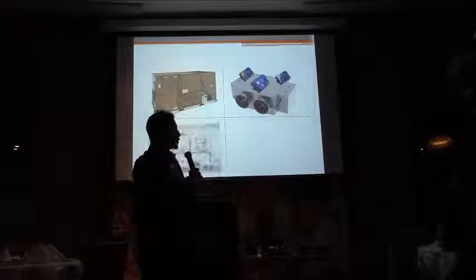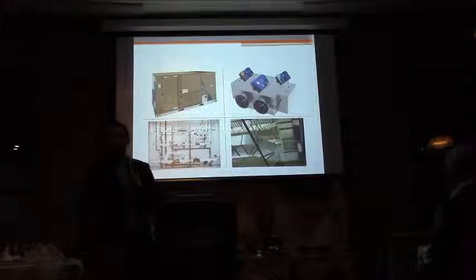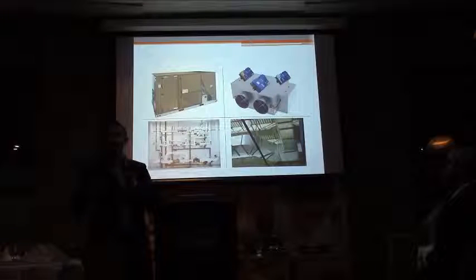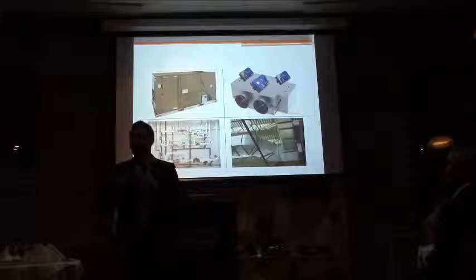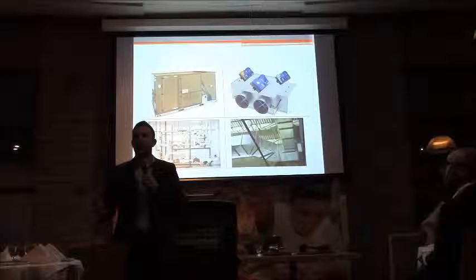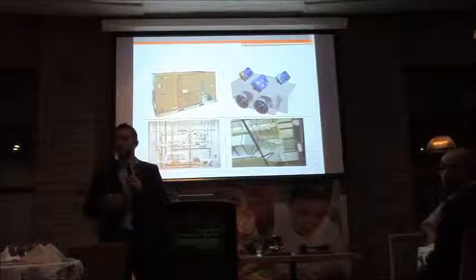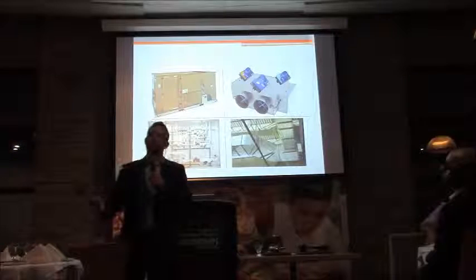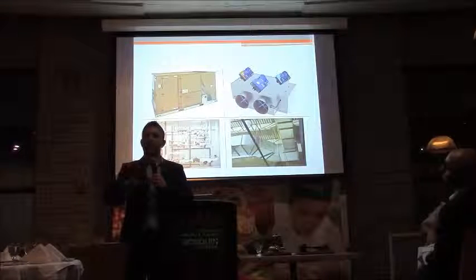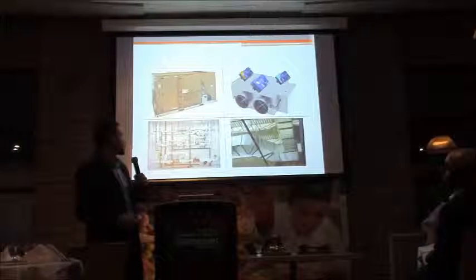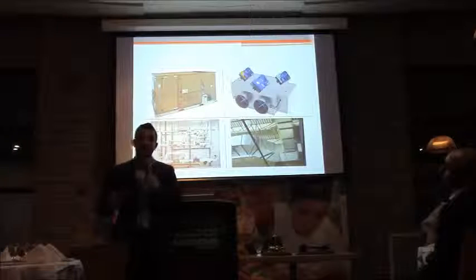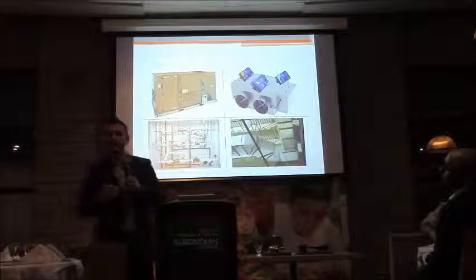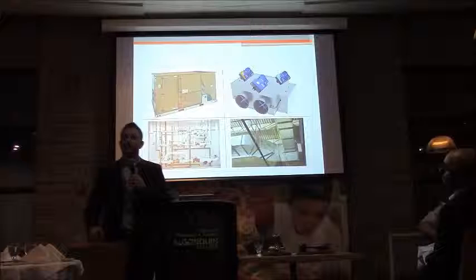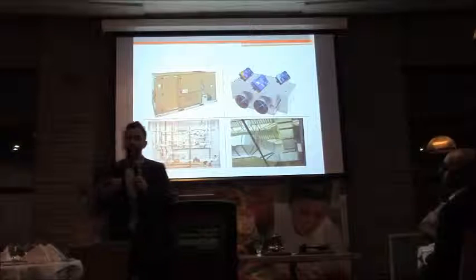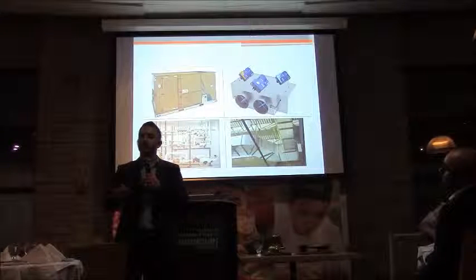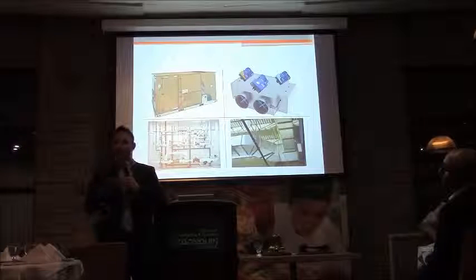The reason I'm presenting high induction: yes, there's the hype, but the hype is there for a reason. We're investing much more money nowadays in high efficiency HVAC systems. Comfort is becoming very important. You want your occupants to be comfortable. If you're designing an office building, for example, you want your employees to be comfortable, because if an employee is comfortable, he's going to perform better at work, and you're going to reduce absenteeism. So it's a question of comfort, but also a question of energy saving. We're seeing more and more air handlers that are variable volume. Variable volume systems are great for energy savings, but they pose a challenge for the selection of your air diffuser. For example, if you're modulating your airflow from 400 down to 100 CFM per diffuser, are you going to select your diffuser for maximum airflow, or for minimum airflow?